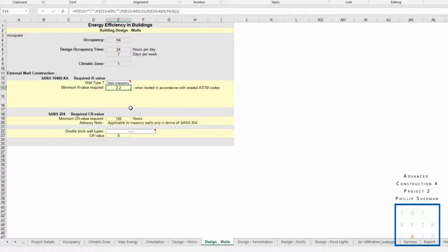Air can also benefit your application because it helps determine how much resistance you can actually have if you had to place your materials right against the sheet metal for the existing building, or if you actually create a little bit of a gap to help with the resistance to apply less materials, because even your air has a resistance value.